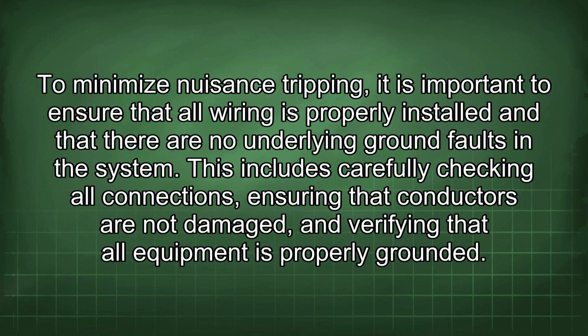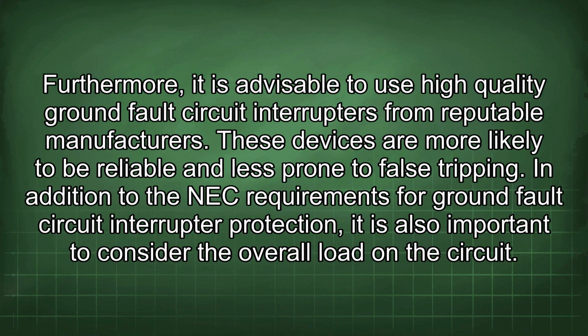To minimize nuisance tripping, it is important to ensure that all wiring is properly installed and that there are no underlying ground faults in the system. This includes carefully checking all connections, ensuring that conductors are not damaged, and verifying that all equipment is properly grounded. Furthermore, it is advisable to use high-quality ground fault circuit interrupters from reputable manufacturers. These devices are more likely to be reliable and less prone to false tripping.